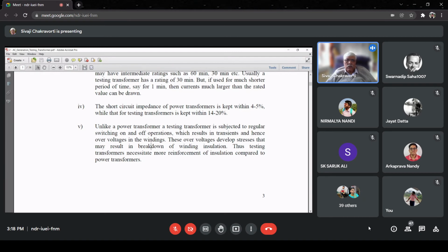So if you look into the nameplate of any power transformer, you will find that it is typically 4 to 5%. We generally don't go above that. Any idea why? Why not 10%? Why not 15%? Because a high short circuit impedance has one advantage. From an engineering point of view, if it is 5%, you can make a reverse calculation that if there is a short circuit, your current will be 20 times your normal current, because it is 5%. Very simple calculation. So if I increase the short circuit impedance, my short circuit current goes down. So that's automatically a type of protection of the system. But we don't do that. Why? It is typically 4 to 5%.